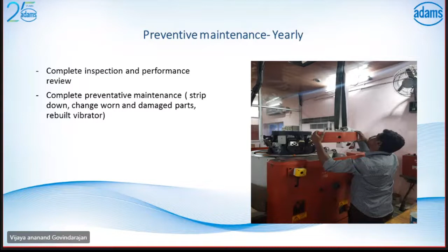Once the armature is removed, we can see the field coils. We will check the resistance and insulation of the field coil, and if there is any damage, we will repair it. And we will check for damage to the diaphragm, guide shaft, as well as the bearing and the trunnion shafts and the trunnion bearings, and we will couple it with the slip table and check the performance of the slip table by doing a couple of tests, observing the plots. If any abnormalities are observed, we will rectify them and we will give the full performance review.